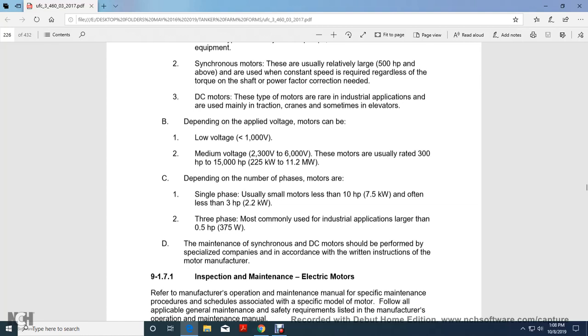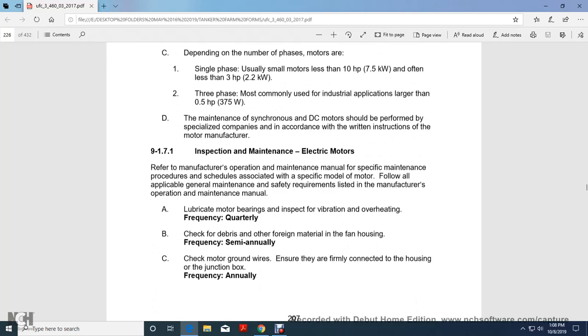Depending on the number of phases, motors are single phase, usually small motors less than 10 horsepower, often less than 3 horsepower. Three phase motors are most commonly used in industrial application, larger than a half a horsepower. The maintenance of synchronous and DC motors should be performed by specialists in accordance with the written instructions of the motor manufacturer. Inspection and maintenance of electrical motors: refer to the manufacturer operation and maintenance manual. Specific maintenance procedures and schedules are associated with the specific model of the motor. Follow all applicable general maintenance safety requirements listed in the manufacturer operation and maintenance manual.